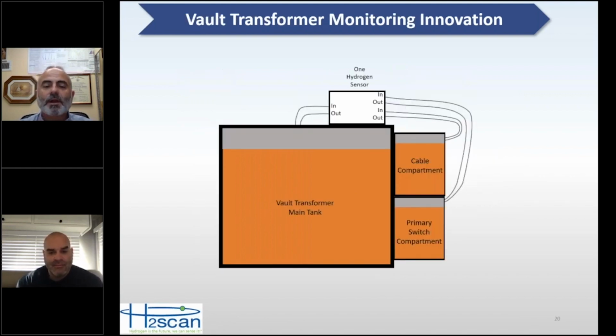Another innovation is on vault transformers. Vault transformers actually have 3 compartments. Well, depending on the design, some have 1, some have 2, some have 3. There's at least one vendor that I'm aware of that is addressing this. If you're going to install monitors on all 3 compartments, having 3 monitors per transformer, you can very quickly spend more on the monitors than the cost of the transformer. So, of course, that's very difficult to justify. And so what they're doing is equalizing the pressure across all 3 compartments and monitoring the gas through one hydrogen sensor to tell if any of the compartments in that transformer are generating hydrogen. Okay, so it's a very innovative way to do that.